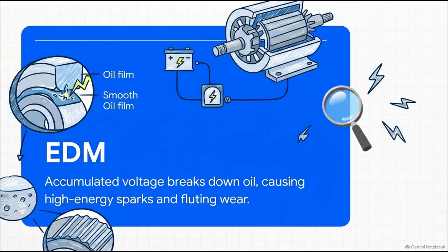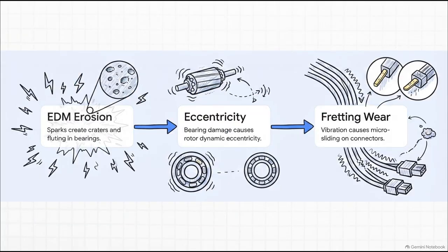These tiny high-energy sparks blast microscopic craters right into the bearing metal. Give it some time and this creates a washboard-like pattern called fluting. It totally ruins the bearing, burns up the grease, and causes some really severe mechanical vibration. The motor is literally eating itself alive. That initiates a pretty brutal three-step cascade. Step 1, of course, is that EDM bearing erosion we just talked about. But it gets worse. Step 2, the chewed-up bearing makes the whole rotor physically wobble. It shifts off center by more than 0.05 millimeters. Engineers call this dynamic eccentricity, and it shakes the entire system.